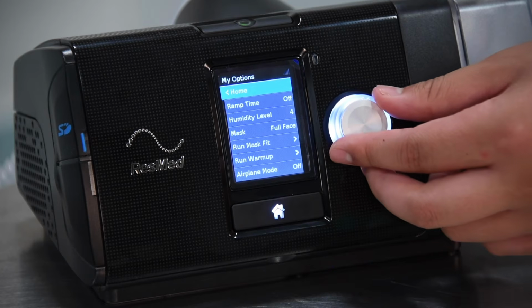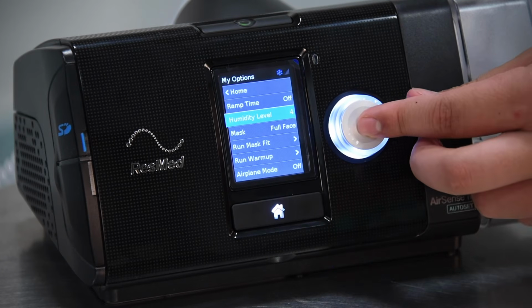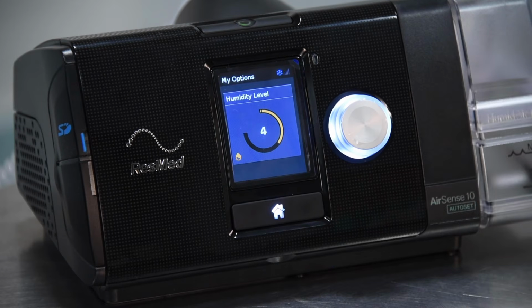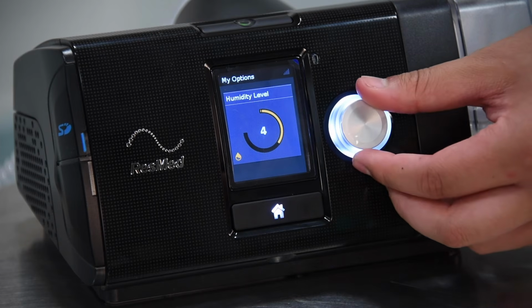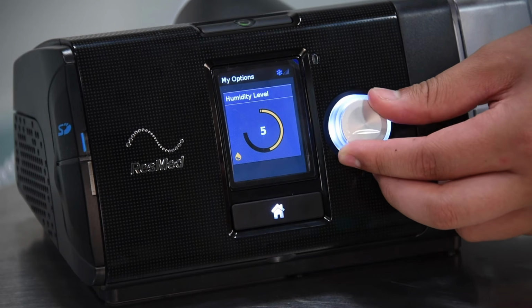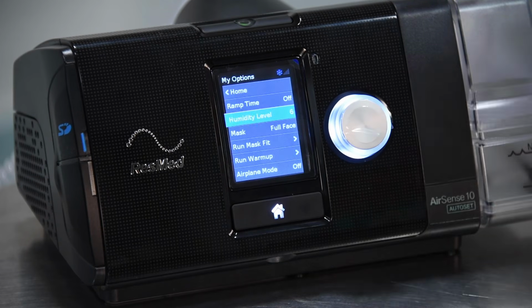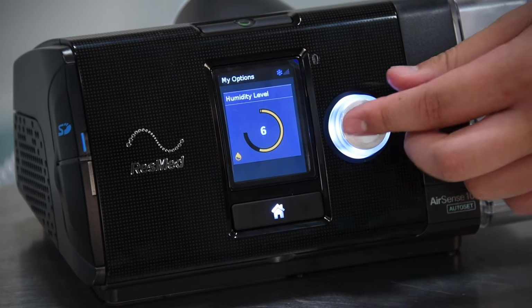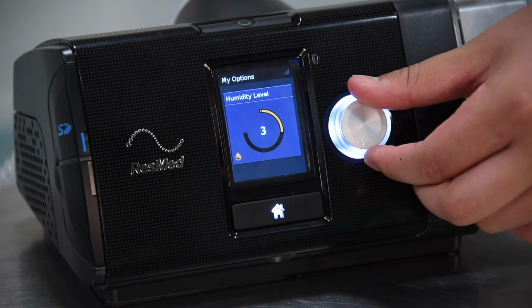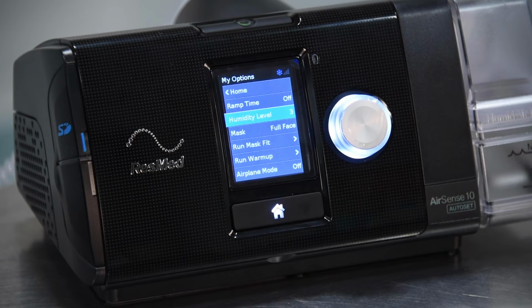Firstly, scroll down to humidity using the silver dial and push the silver dial in. You can alter the humidity settings depending on if you are suffering with a dry mouth. If you do suffer with dryness, then turn the humidity up by selecting a higher number with the silver dial. If you experience water in the tube, also known as rainout, then reduce the humidity settings and select a lower number. To confirm your humidity choice, push the silver dial to store your settings.